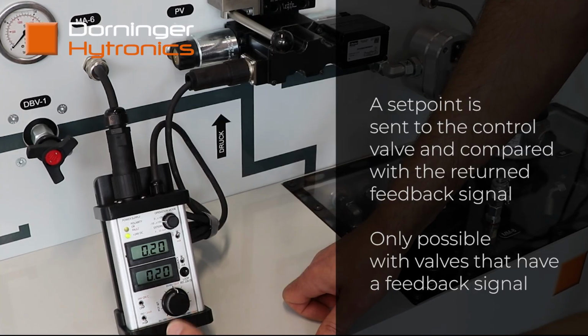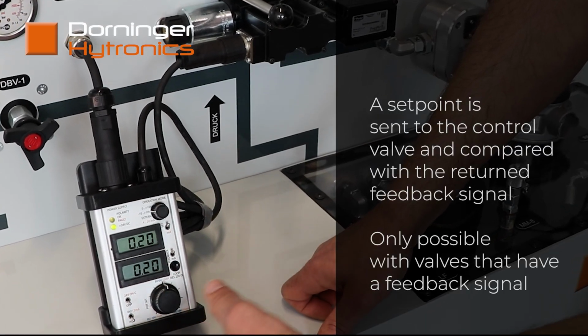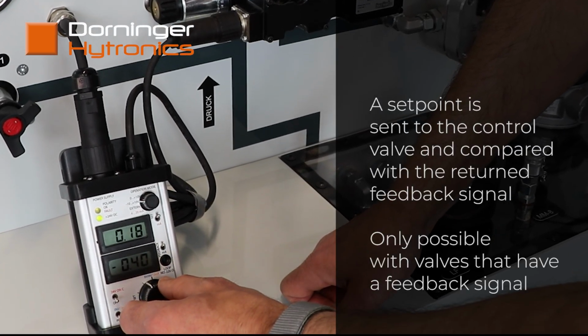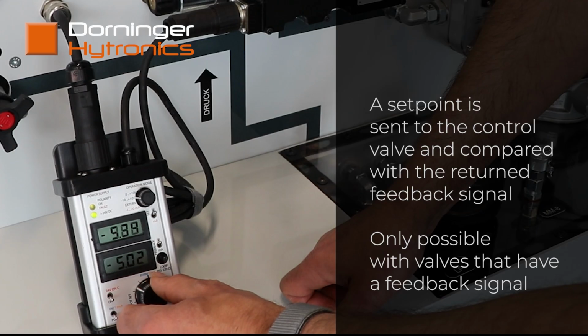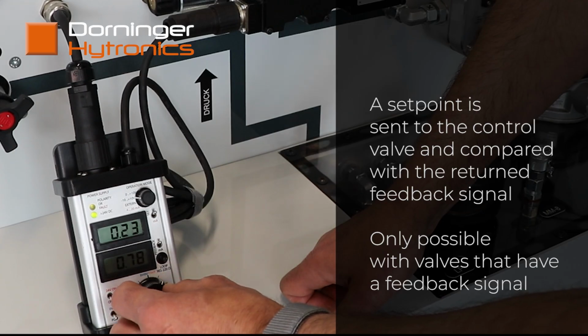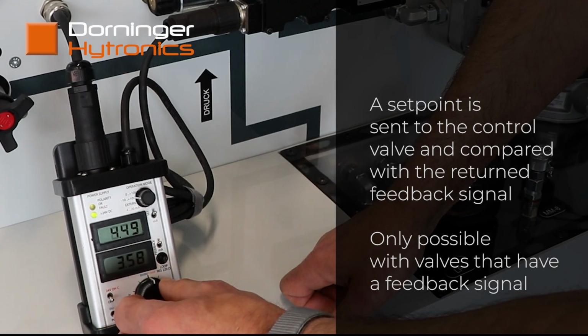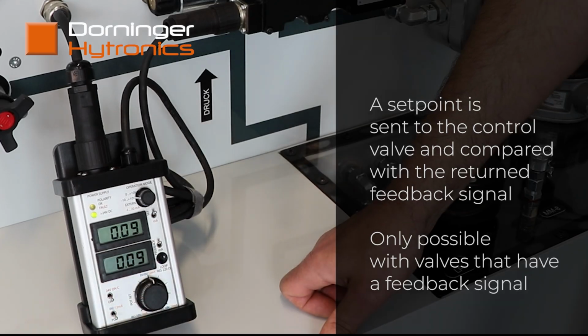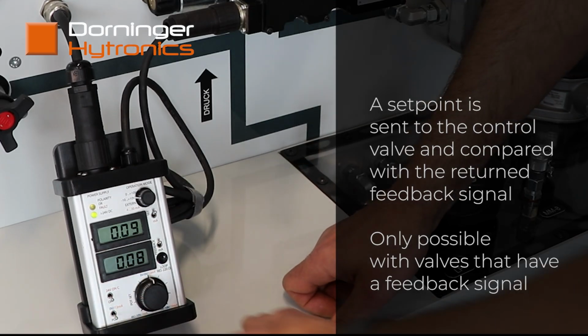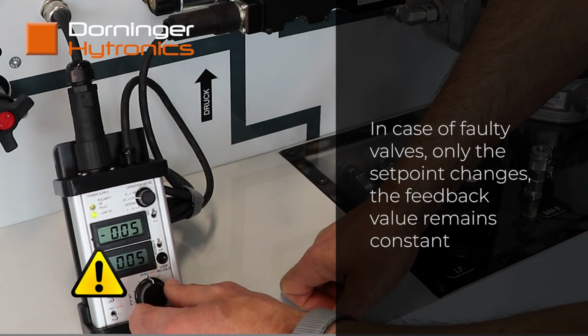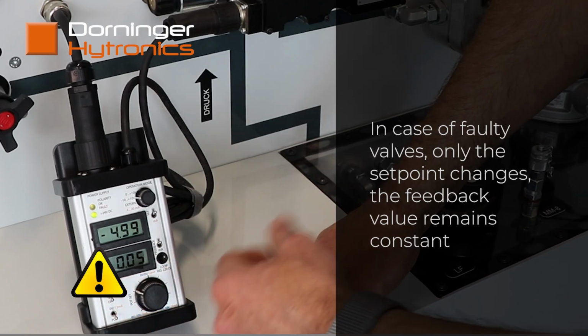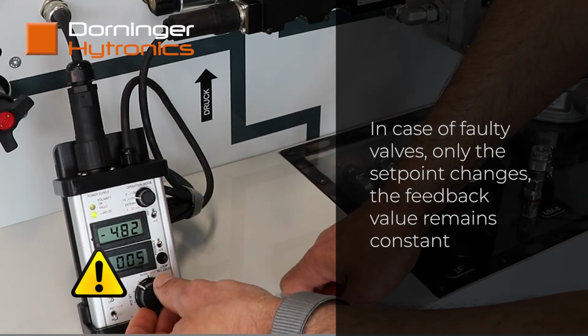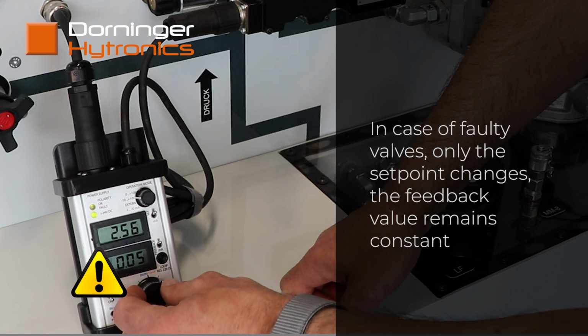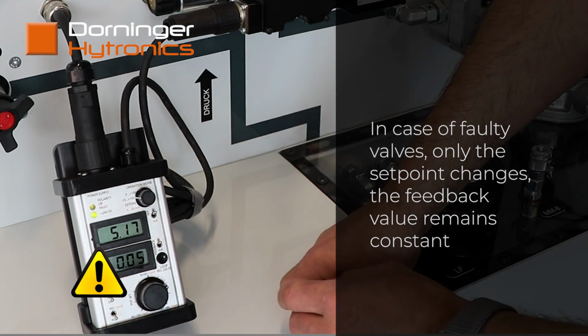Depending on the ambient noise level, the movement of the spool may also be audible. From a technical perspective, the Vbox sends a setpoint signal to the control valve. The valve is functioning correctly if the setpoint signal and the feedback signal approximately correspond. If the valve is not functioning properly, for example if the valve spool is stuck, the feedback signal will not change when the setpoint signal is varied. The setpoint signal changes in the upper display, while the lower feedback signal display remains static.